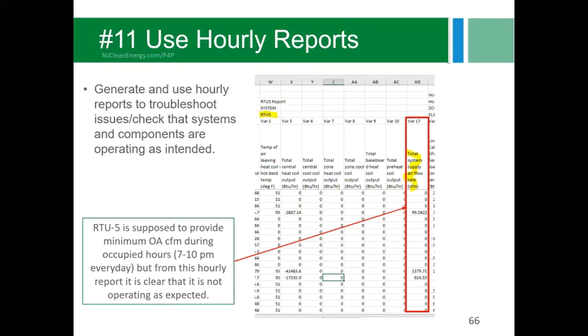Lastly, utilize hourly reports. Here's an example where the submitter thought their unit was operating as variable air volume and providing minimum outside air rates during occupied hours. But running a quick hourly report, you could see the unit is actually cycling off, because for most hours in a 24-hour period it's supplying absolutely zero CFM to the space. So if you're ever trying something new or not sure, just run a quick hourly report. They're so valuable in troubleshooting and identifying issues, and that will really help reduce review iterations.